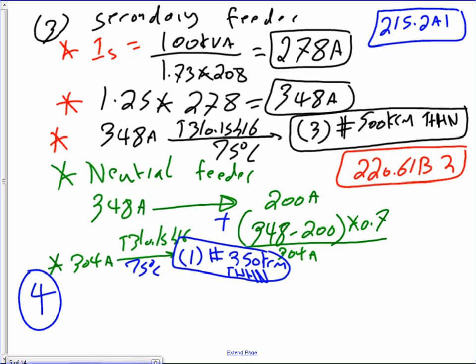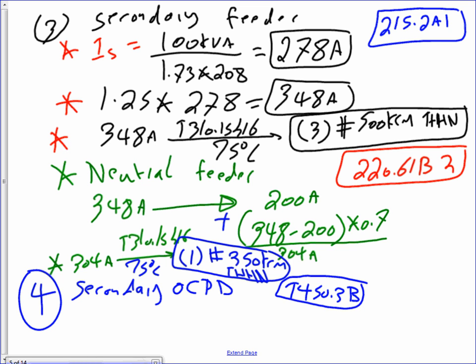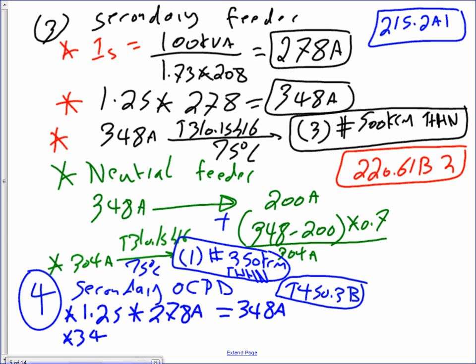The last one, guys, that we're going to do is secondary overcurrent protection device. If you guys go to table 450.3(B), we were just there, it will tell you that you take 1.25, multiply that baby by the 278 amps. That will get you 348 amps. And then you take the 348 amps, take it to 240.6, like we have done everything else.